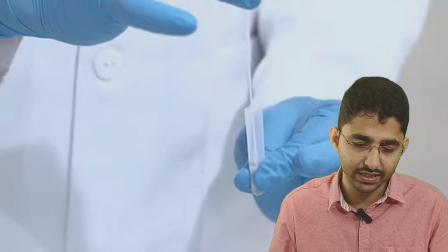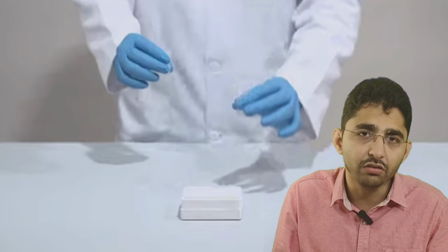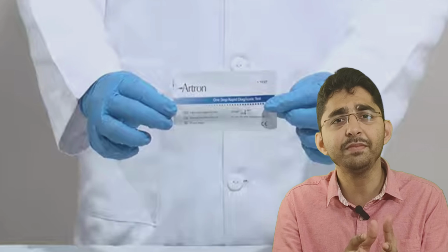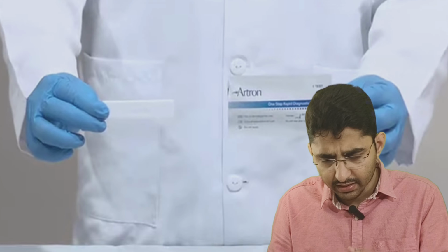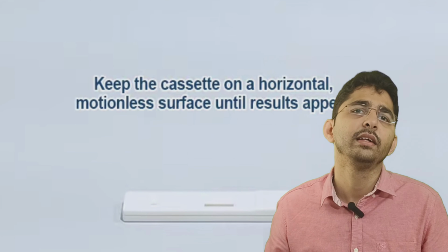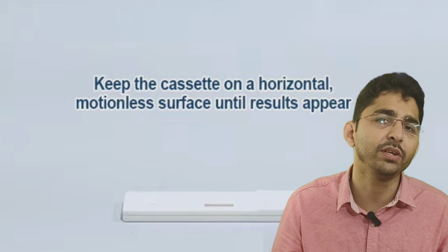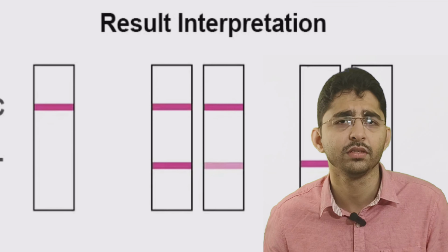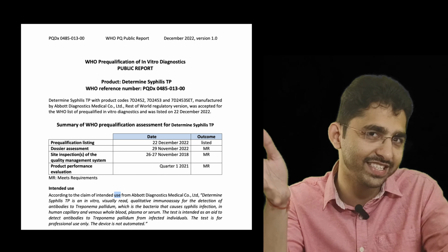So they will assess the clarity of the IFU, the consistency, the formats, the technical contents, the easiness of the IFU, and many more. When this has been done, at the last, in the third step, the WHO PQ team will let the manufacturer know on which areas they need to amend their labeling information before getting it as a PQ listed product. So the WHO team will give the recommendation and the manufacturer is going to address those comments in the labeling review, and finally my product will be PQ listed.